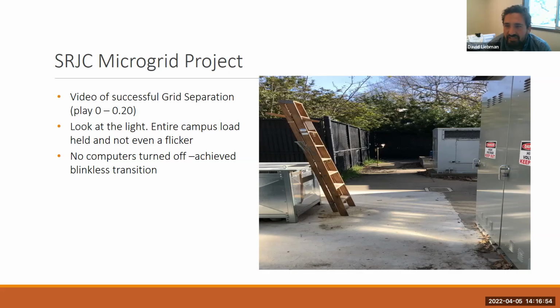On the right-hand side in the picture, in the background, there's a lamp that's glowing. In the video, you'll see that we essentially go into an island condition where the main breaker opens and nothing happens. It's kind of anticlimactic because the light doesn't flicker at all. But that means that in less than 30 milliseconds, we separated from PG&E and maintained the entire Santa Rosa campus. No computers turned off, nothing even blinked. That's about 21 buildings and close to 1,000 kW load, equivalent to over 1,000 homes, that we instantly power without anything dropping. It's the first system of its kind achieving this at that larger scale, and we're continuing to showcase and validate it. Right now, our current study is working on how to tune the reconnection to have a seamless reconnection to the utility, and we're working on that with PG&E.